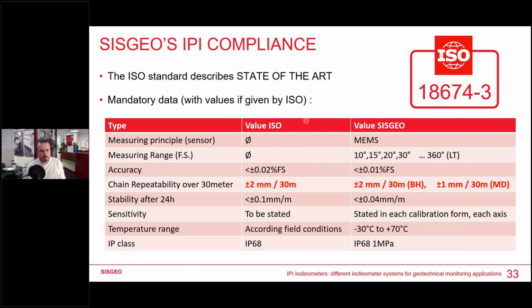Here you can see the ISO, the first column is the values or the data that the ISO norm requests on each data sheet of the provider. So if you want to purchase a device that is ISO compliant, please pay attention to these values that are mandatory. We are, of course, providing all these values in our data sheets, and all these values, as you can see, are compliant. Just here notice that the repeatability over 30 meter for us is the most important because accuracy of the probe is important.